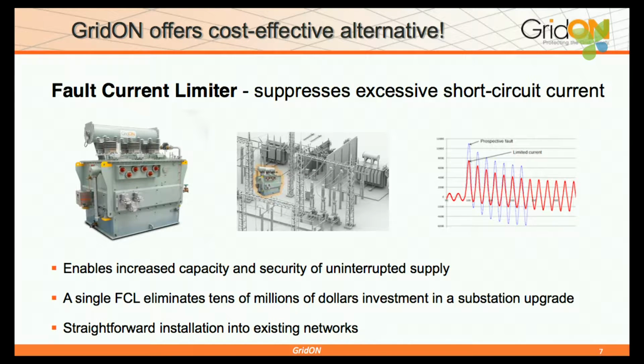This is how the product looks like. It sits in a substation, can sit in a distribution, transmission, or an industrial plant substation. And its whole purpose in life is, when there is a fault situation, to actually choke the current level from the prospective level down to what the protection equipment can handle.